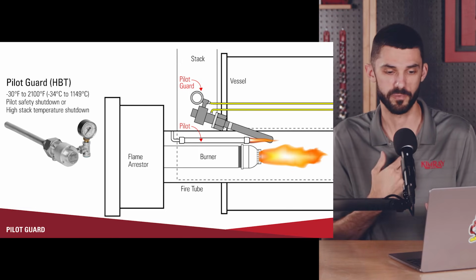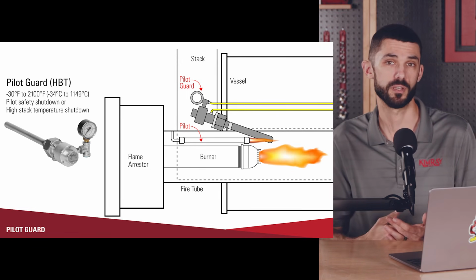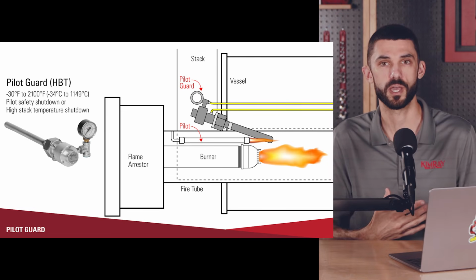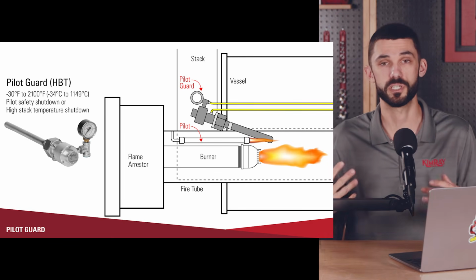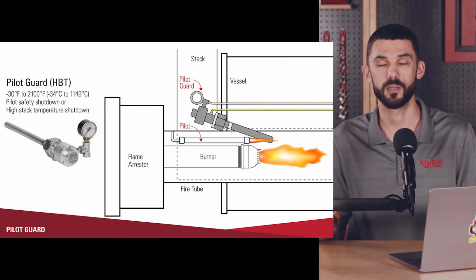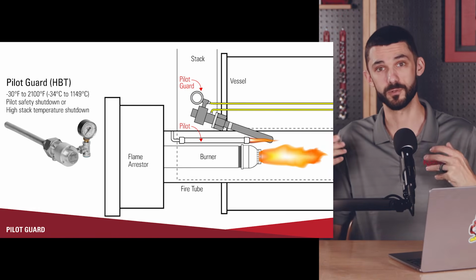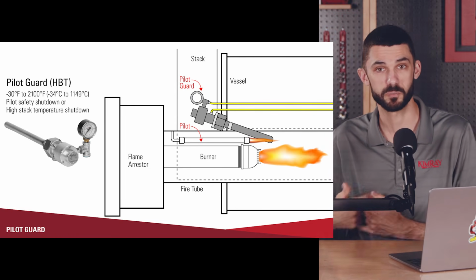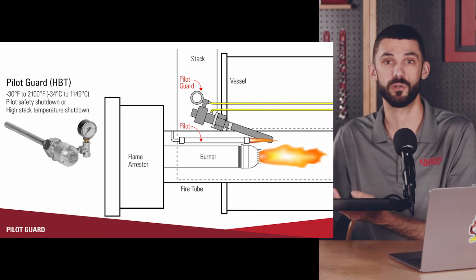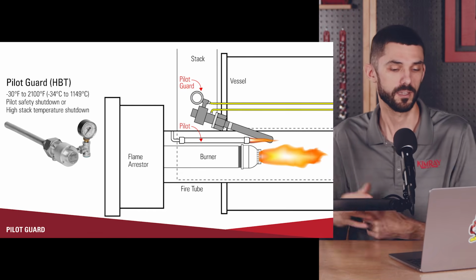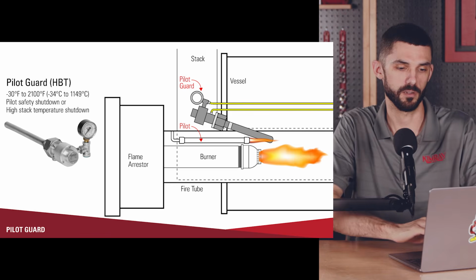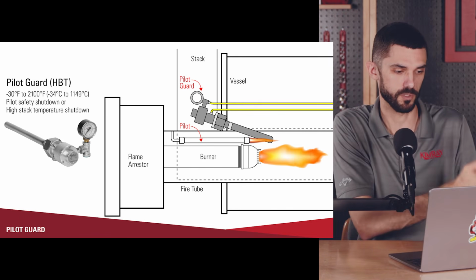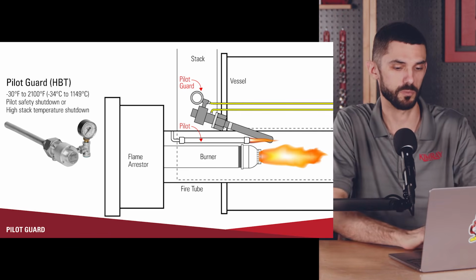So if the pilot flame ever got blown out or is not present, there's no way for that burner system to come on, because if there's no pilot flame there and you open up a burner valve, you're going to be spraying natural gas into the burner, but nothing will be igniting. And so the pilot guard is, again, just another step in that process to get to heating your vessel.